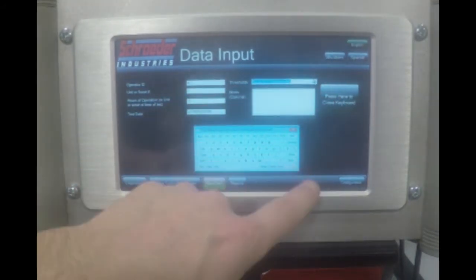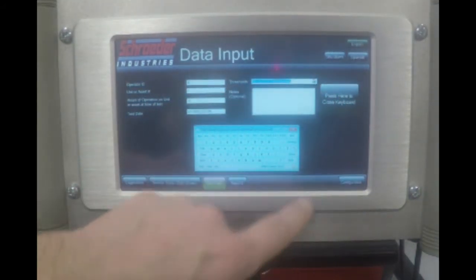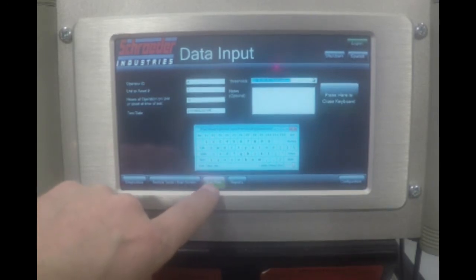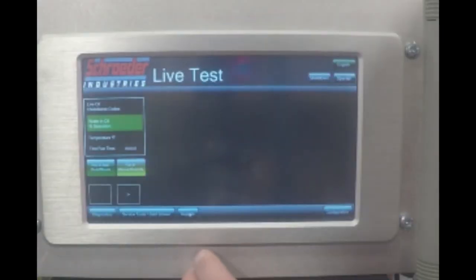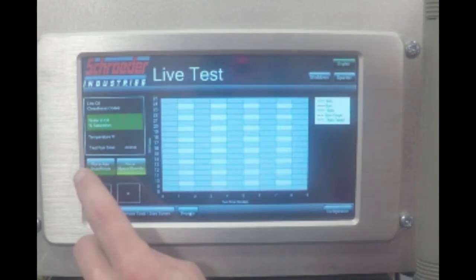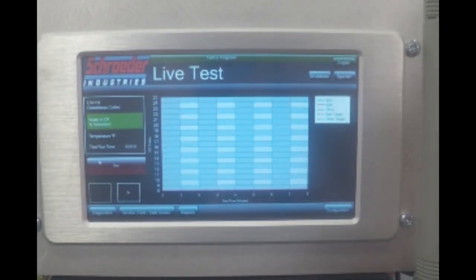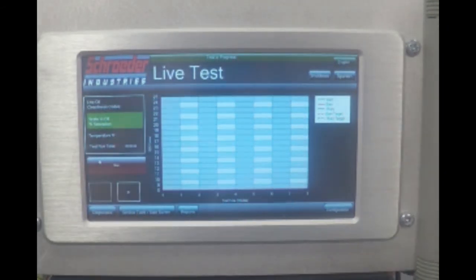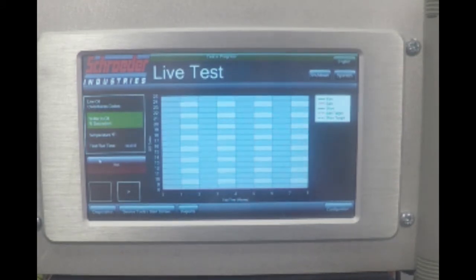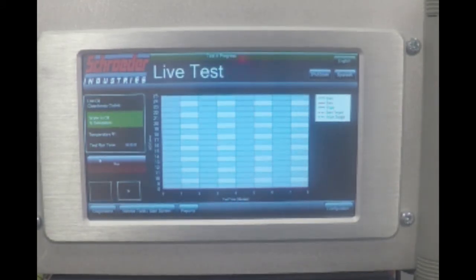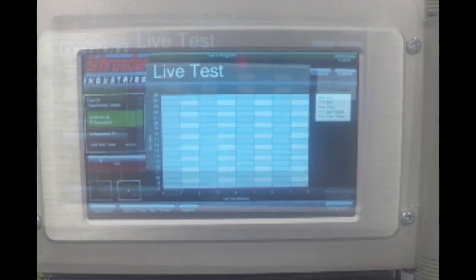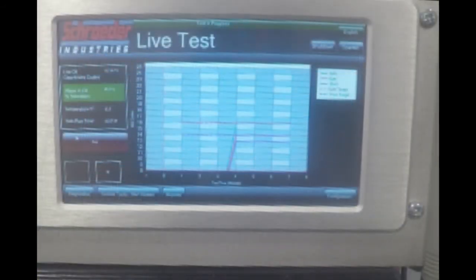You can input notes — this is optional and only for your own reference. After that, you're ready to start the test. Choose either auto mode or manual. In auto mode, the unit will filter down to the selected ISO class and shut down automatically. In manual mode, the unit will run continuously. When the desired ISO class is achieved, the filtration will stop and a pop-up message will appear on screen.